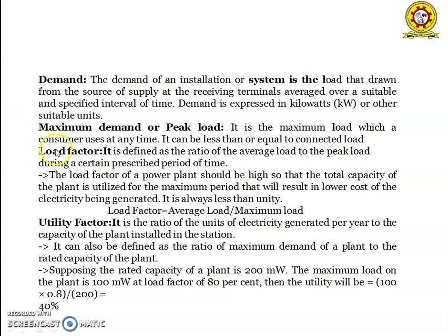Next one is the load factor. It is defined as the ratio of average load to the peak load during a certain or prescribed time period. The load factor of a power plant should be high so that the total capacity of the plant is utilized for the maximum period, which will result in a lower cost of the electricity being generated. It is always less than unity. A higher load factor is a desirable quantity.